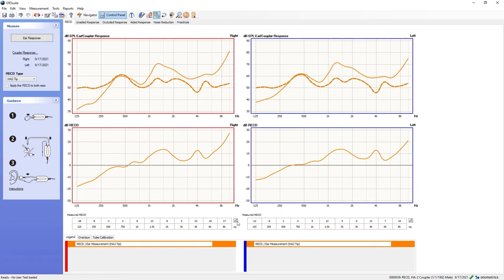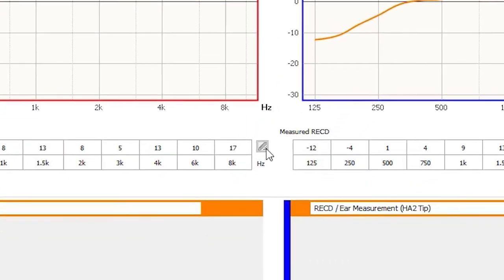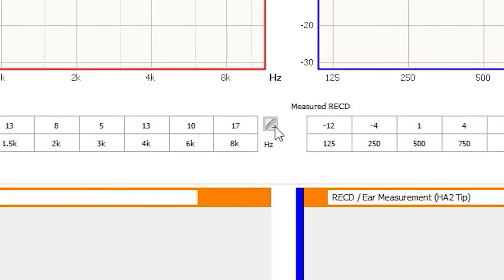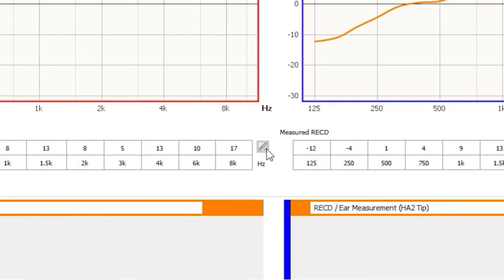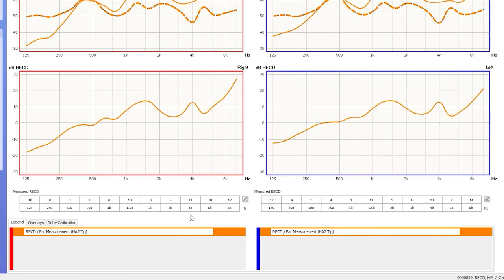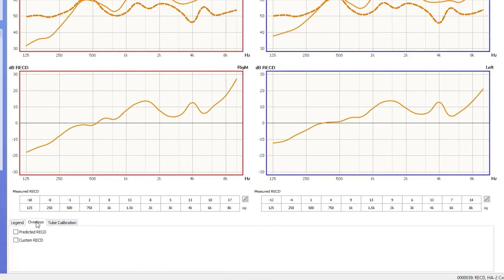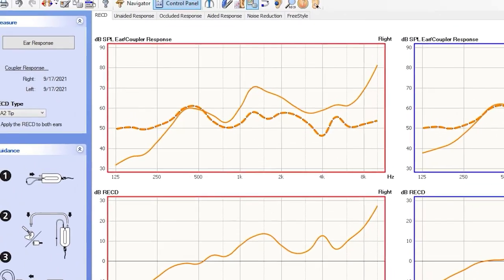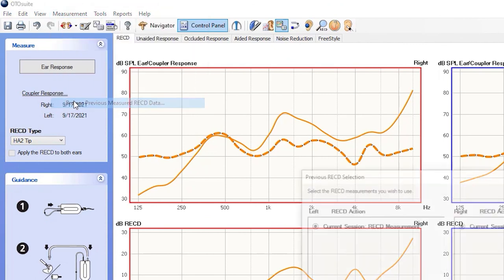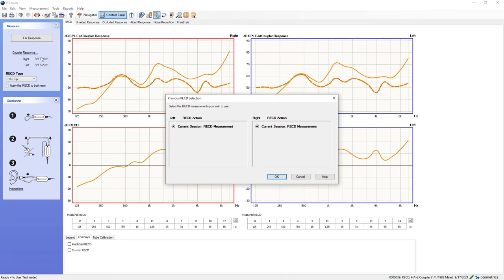To enter manual RECD values, select the pencil icon to the right of the measured RECD table. The legend table will show measurements completed, and overlays allow the view of a predicted or custom RECD. Finally, you can view a history of the RECDs previously obtained for a client by clicking Measurement above the toolbar and selecting Browse Previous Measured RECD Data. The measured RECD data can now be used for coupler-based fitting with the Aurical HIT test chamber.